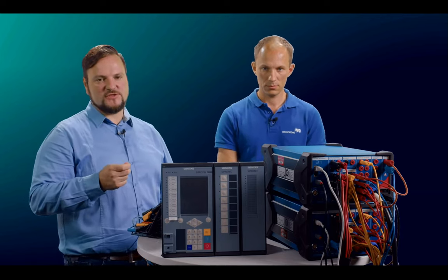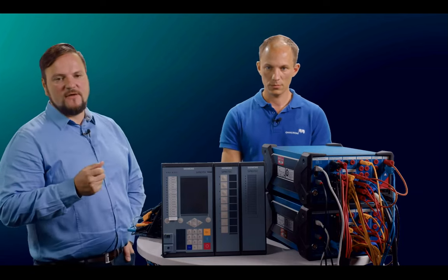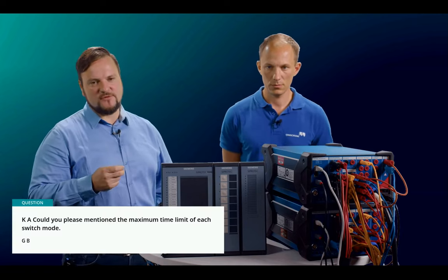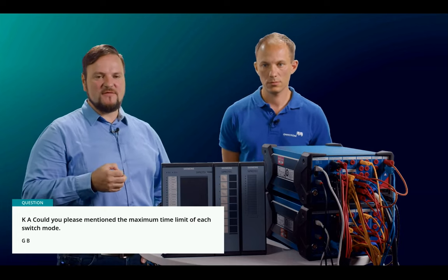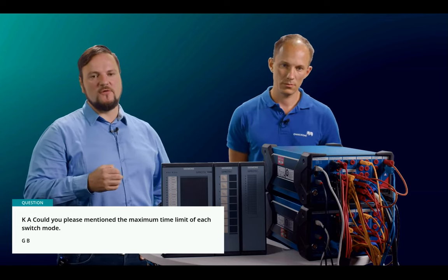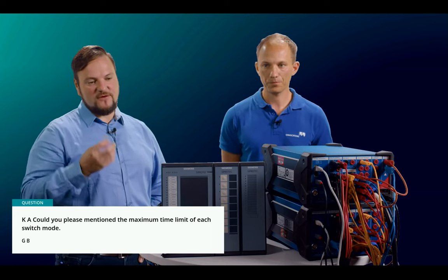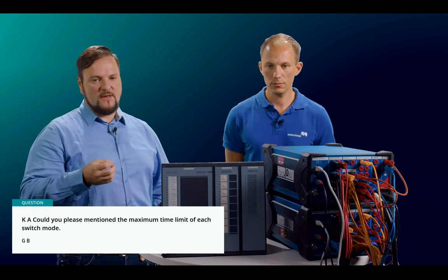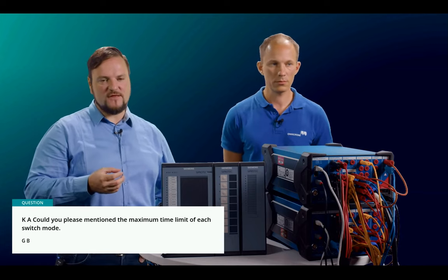Okay, then next question, GB. Could you please mention the maximum time limit for each switching mode? I think for the fast mode, it depends on how fast the voltage is running down and also the frequency is running down on the motor bus. Due to that, the device or the algorithm is calculating the time or the switching mode. So we can provide the fast mode in 10 milliseconds.